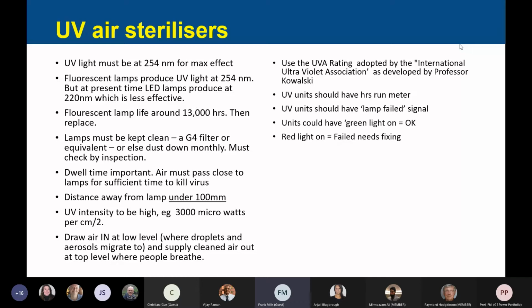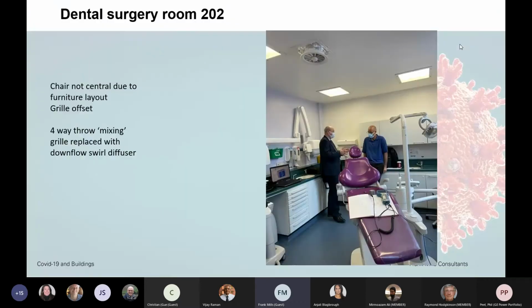It's a good idea, if you have any of these units, to know how long they've been running. So have a meter on it or a BMS connection that tells you the UV unit has been running for 10, 11, 12,000 hours, 13,000 hours. You know it's about time to change the lamps. It should have a lamp fail signal as well, so you know that it hasn't worked, because it could look like it's working but not doing any work, and then you have a dangerous situation. So get some lighting on the unit, which gives you that.